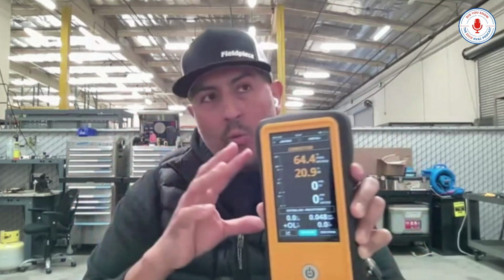And for your carbon monoxide generation, what NCI teaches is that you for sure want to be under 100, 99 or below in the flue. However, under 50 would be even better than that. But generally, those are the ranges that you're looking for just to ensure that you're getting as close to complete combustion as you can, right? In the real world, we're not looking for complete combustion because that's not possible. But we're looking for the most complete and finding the right mixture of air and fuel and heat to get almost complete combustion. Fantastic.